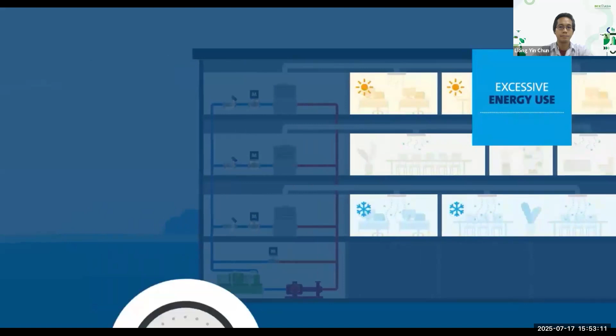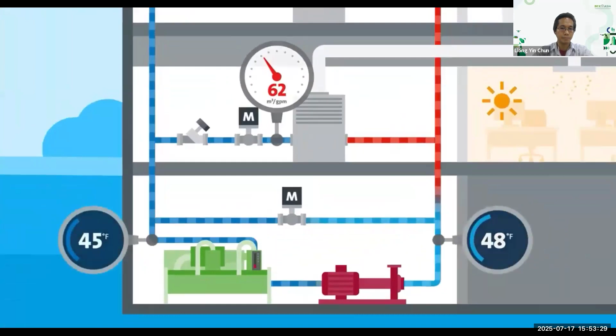Inadequate commissioning leads to poorly balanced systems and excessive energy use. An incorrectly balanced system will result in having terminal units receiving more or less flow than necessary. This could also lead to low delta T. This is especially apparent at part load conditions and results in less comfort.